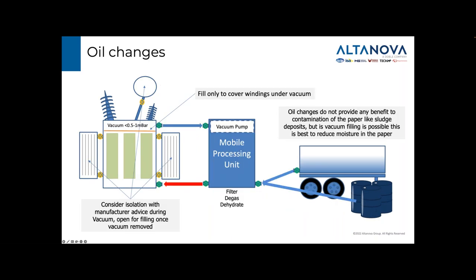When filling the transformer back up, by far the best method is to pull a vacuum with a mobile processing unit to dry the windings, but also to fill under vacuum, as it improves impregnation of the oil into the windings and minimizes the chance of residual air pockets. However, even if a transformer has been rated for vacuum, it may no longer be suitable for vacuum due to deterioration or damage of the asset in service, or there are accessory changes to ones that are no longer rated. Assess each transformer on its own merits, and if in doubt, do not pull vacuum. It's much better to get the oil back into the transformer and to perform additional circulations of the oil than risk damage to the asset. When pulling vacuum, it is important to equalize the pressure across the barrier board to prevent damage to this component.